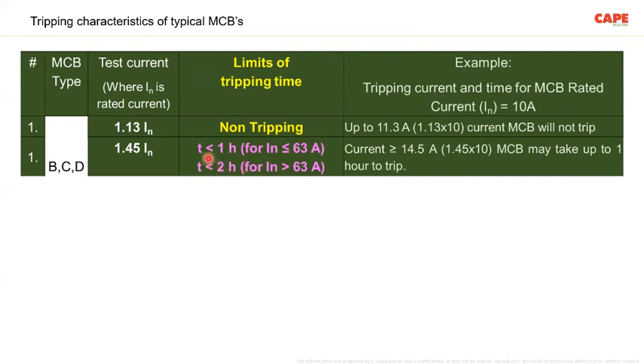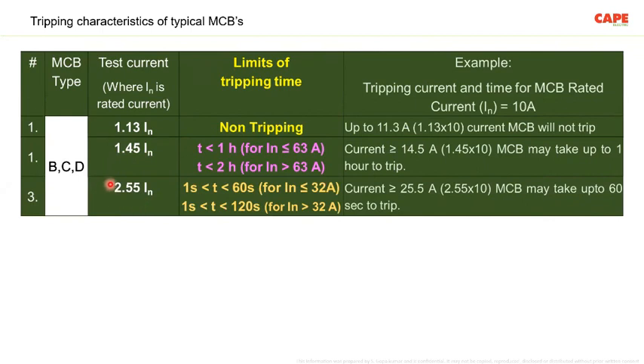This also means your wiring must be able to withstand a higher current for this duration. For example, the wiring must withstand 1.45 times the current for 1 hour for circuits less than or equal to 63 amps, and for circuits greater than 63 amps, a minimum of 2 hours. The next disconnection part of B, C and D type MCBs is an overcurrent of 2.55 times. For an MCB of less than or equal to 32 amps, it can take anything between 1 second and 60 seconds. Higher than 32 amps, it can take 1 second to 120 seconds, 2 minutes, to trip.